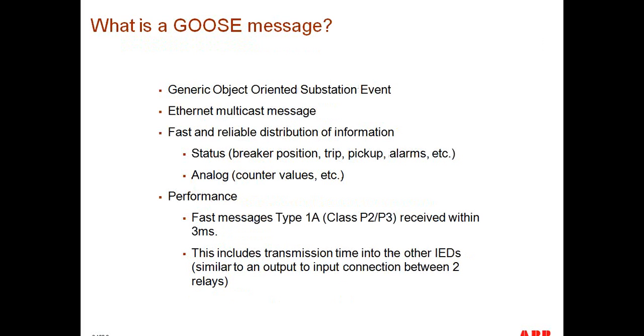So, what is a Goose message? Well, a Goose message is a generic object-oriented event. It's an Ethernet multicast message. It's fast and reliable distribution of information. Essentially, you can send status information, position of breakers, trips, pickups, alarms, just about anything. Any type of information that you can associate with the output contact of your protective relay that you do today can be mapped to a Goose message or exchanged via Goose messages. Another type of information that can be exchanged are analog counters.